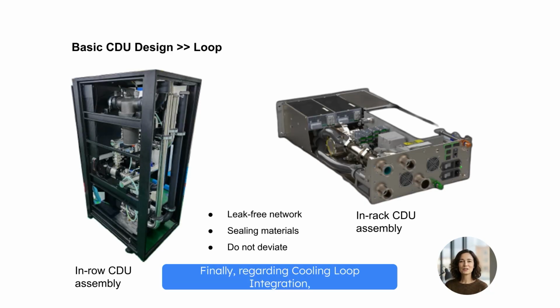Finally, regarding cooling loop integration, the metric is simple: a leak-free network for the entire service life. Look at the complexity in figures. There is no room for error. Whether it's the compact in-rack or the large in-row assembly, every tube connection requires precise sealing materials.